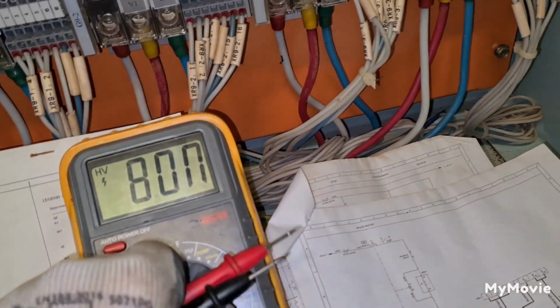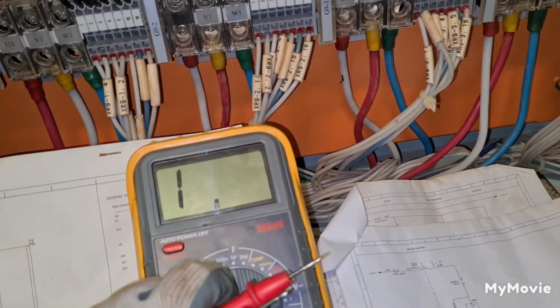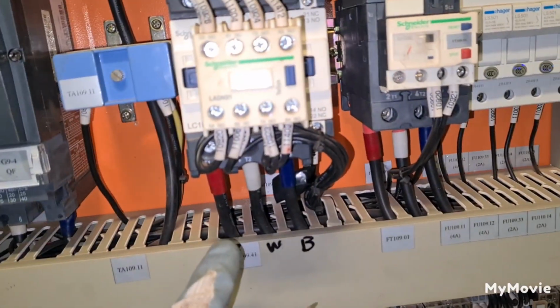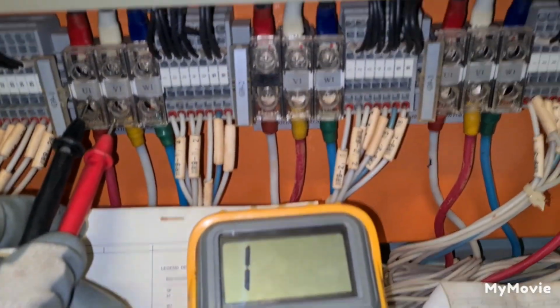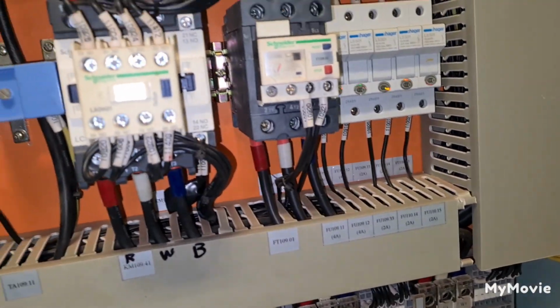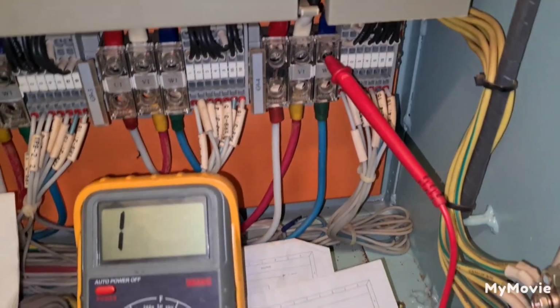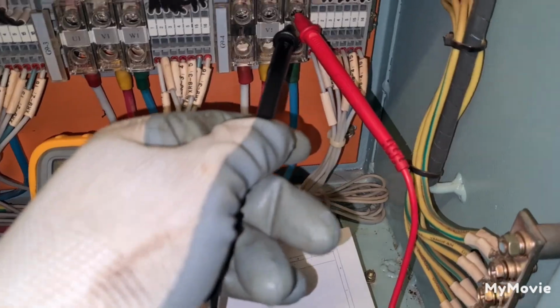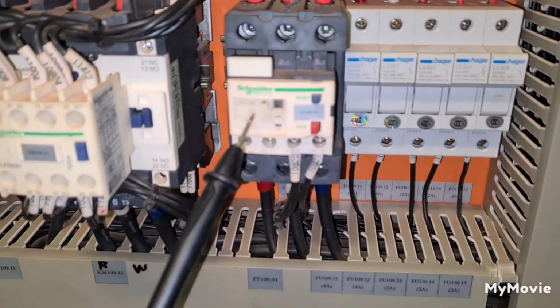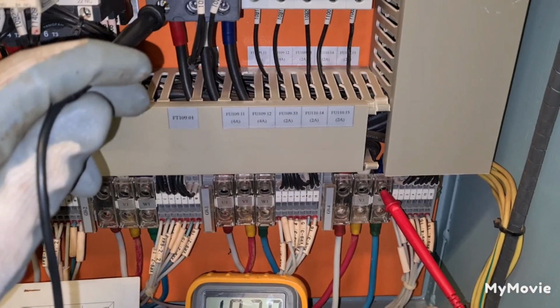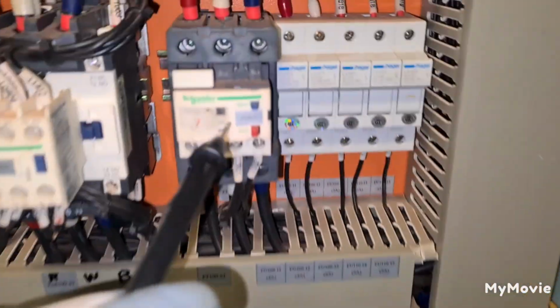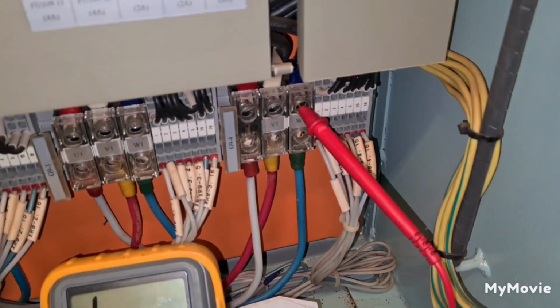Then we can proceed on continuity test. In continuity test, we are going to check all individual contactors from here, there, and there. So to check the continuity, we must check that there is continuity on this side going on this contactor. Okay, this is our contactor for motors. This one, and this one. So we need to check if there is continuity between here and on here, on the thermal overload relay. So as we check the continuity, we have the continuity, meaning this overload relay is going on this side.